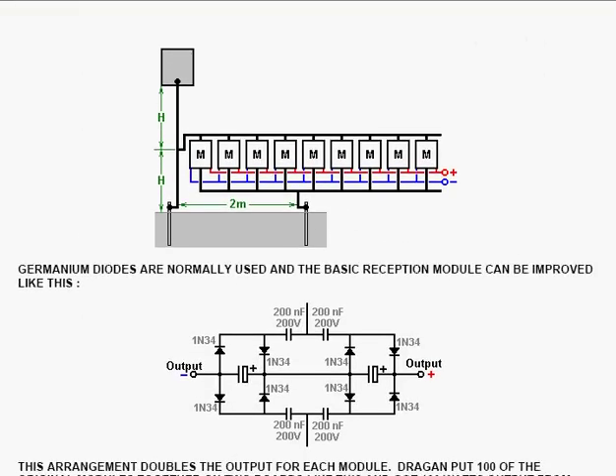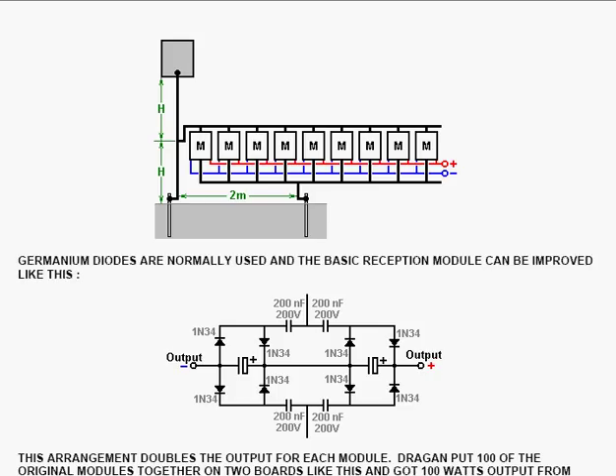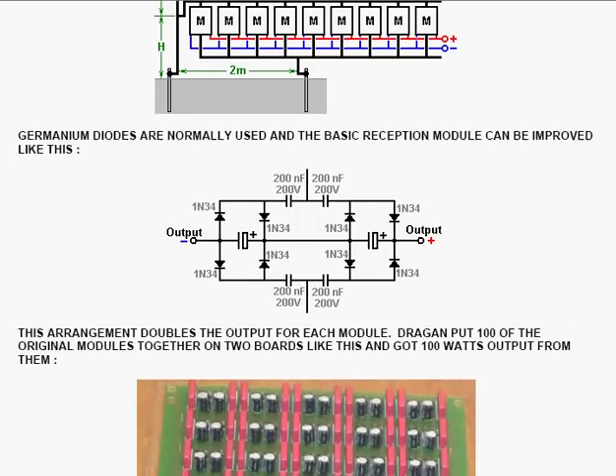Ideally, the modules, marked as M, are connected halfway between the pickup plate or coil and the earth connections, and it's commonly found better to have two separate earth connections. It looks a bit mad this way, with the wire coming straight down to an earthing coil and the modules taken off and down to a second earthing coil, but in actual fact this works very well, though the two earthing rods need to be a reasonable distance apart. In his case, he discovered that 2 meters was a realistic amount.